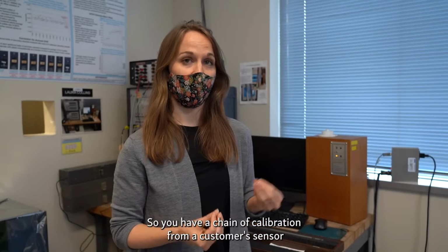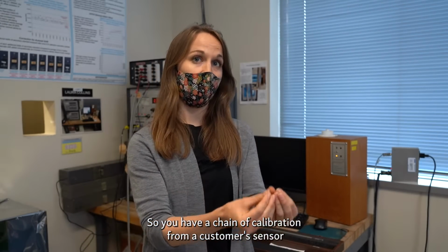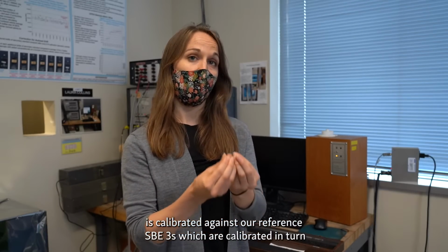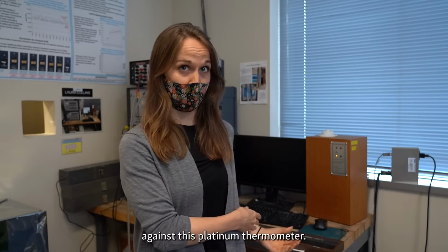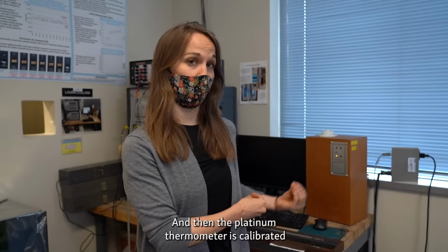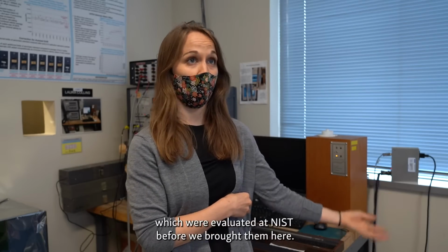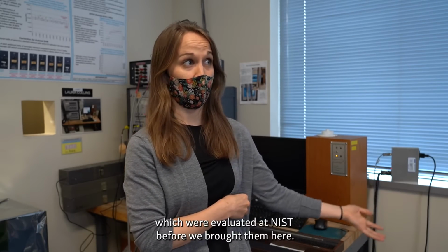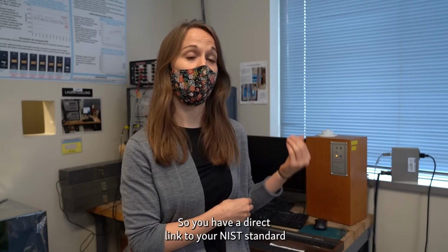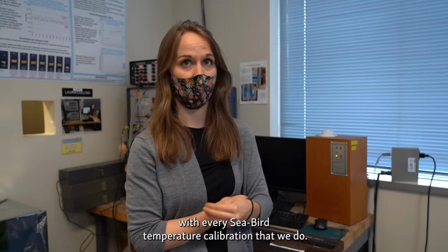So you have a chain of calibration: a customer sensor is calibrated against our reference SBE 3s, which are calibrated in turn against this platinum thermometer, and then the platinum thermometer is calibrated directly against these fixed point cells, which were evaluated at NIST before we brought them on site here. So we have a direct link to NIST standards with every Seabird temperature calibration that we do.